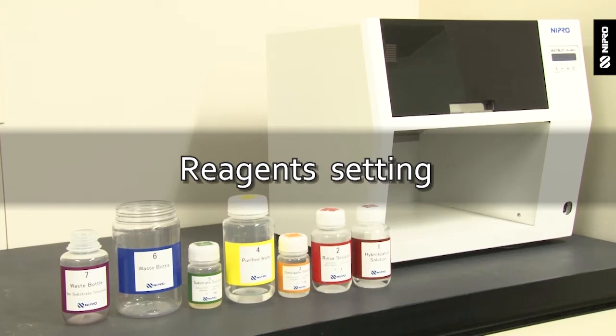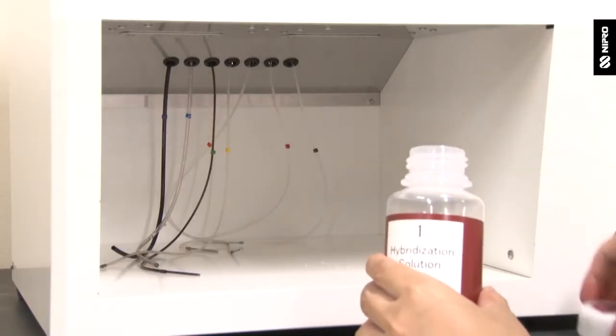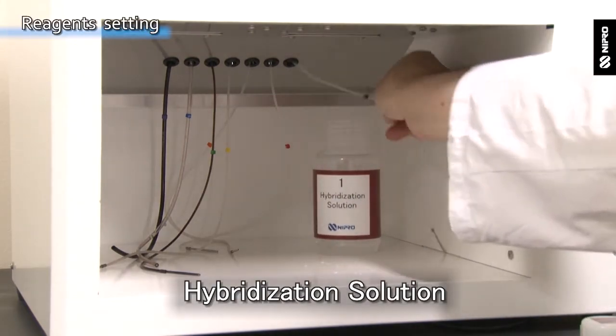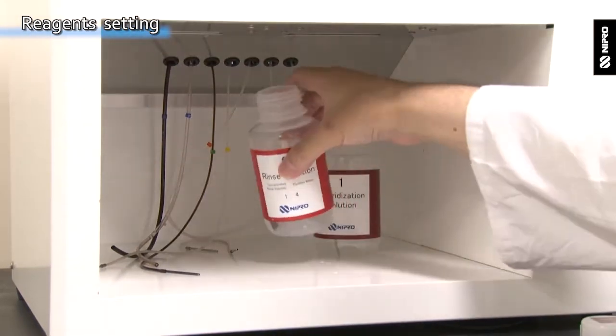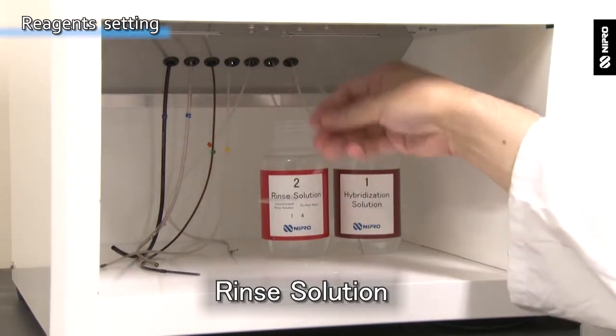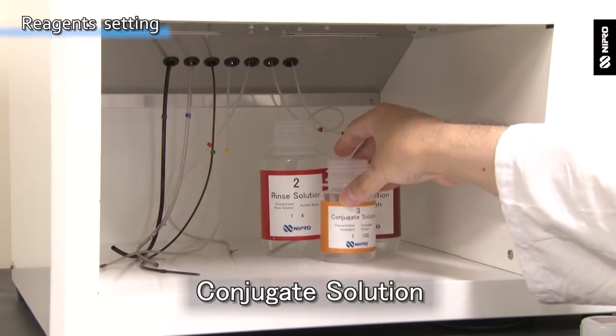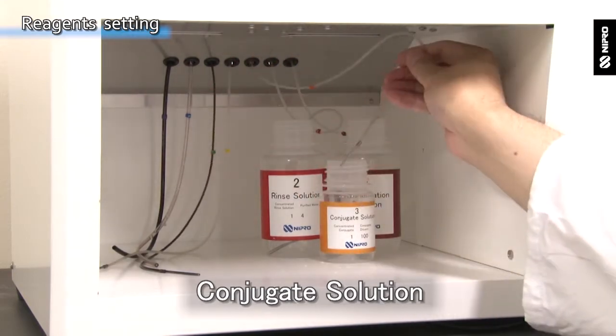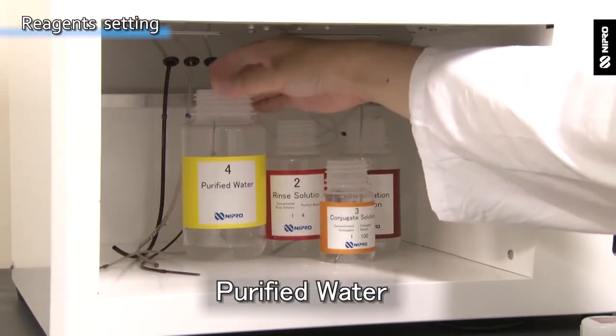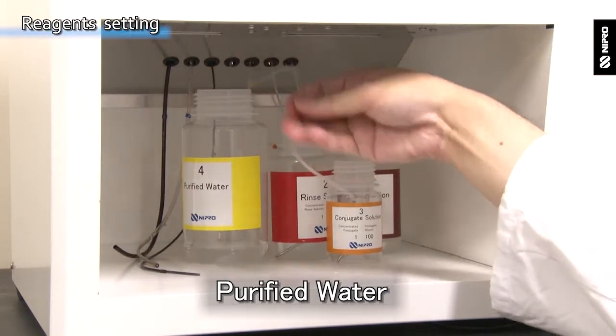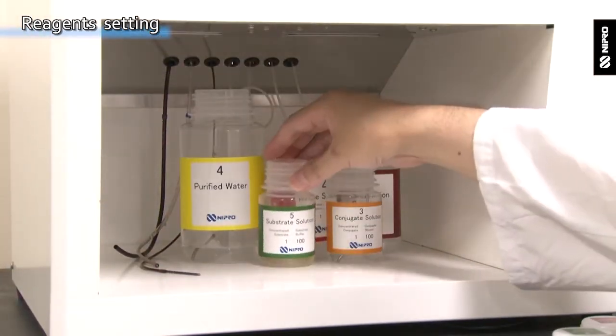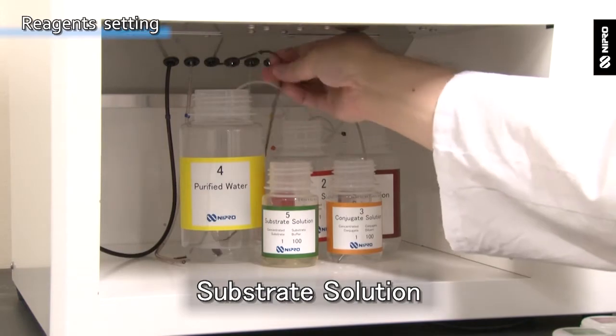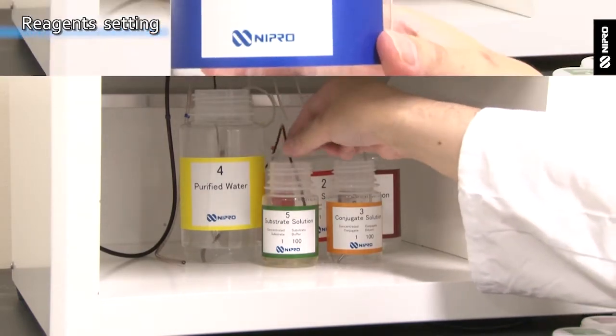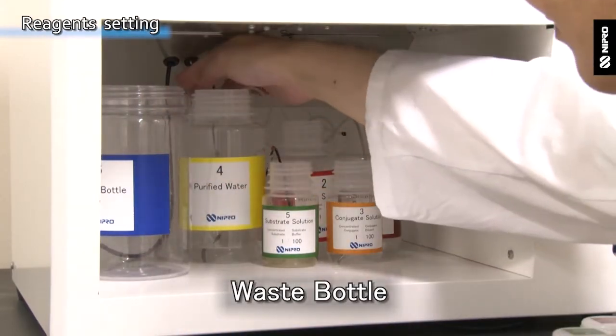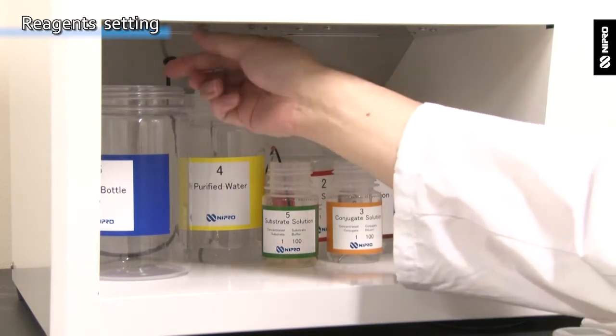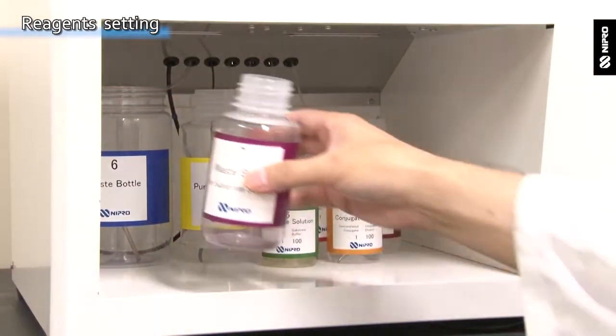These reagents are placed in the multi-blot machine. To the hybridization solution bottle, insert the tube number 1. To the rinse solution bottle, the tube number 2. To the conjugate solution, the tube number 3. To the purified water bottle, the tube number 4. And the substrate solution, tube number 5. Tubes number 6 and number 7 are drain tubes to the waste bottle.